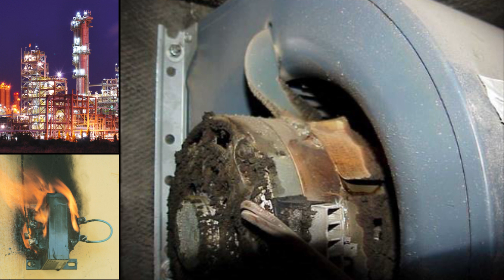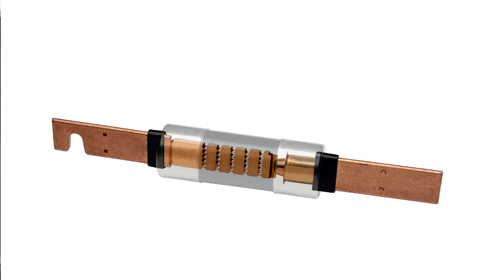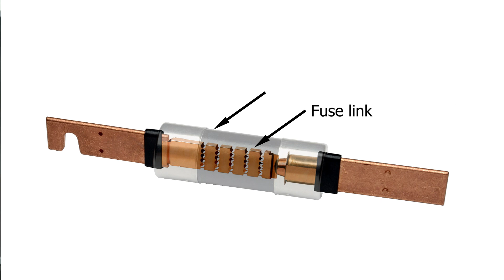Reliable circuit protection is also essential to electrical safety for personnel, as well as avoiding severe monetary losses from power blackouts or prolonged facility downtime. The fuse is a simple and reliable overcurrent protective device that is comprised of a fusible link or links encapsulated in a tube or housing that are connected to terminals. The link's electrical resistance is so low that it acts as a conductor until it encounters current levels above its amp rating. Then it melts and opens the circuit to protect conductors, components, and loads.